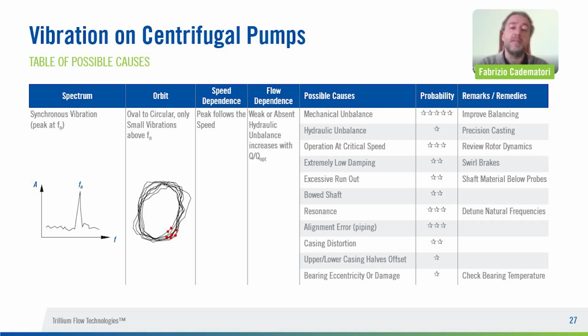The spectrum is characterized by a peak at the rotating speed, and the orbit shape is almost circular or elliptical. The key phasor signal, a red dot, usually remains almost in the same angular position. There is weak or absent flow dependence, especially if you are talking about mechanical unbalance. The common causes are mechanical unbalance located in the coupling or foreign matter stuck in the impeller, hydraulic unbalance due to uneven flow in the impeller, operation at critical speed, and in this case a review of our rotordynamic calculation is required, or very low damping in the journal bearing, or excessive runout, bowed shaft, and so on.